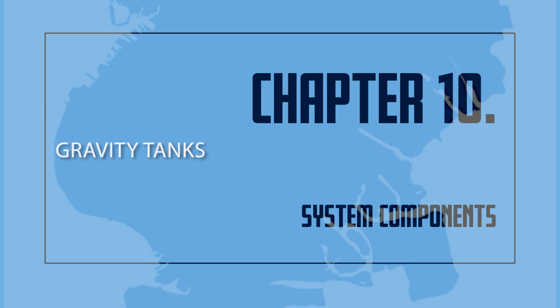All gravity tanks have an overflow pipe that drains off excess water in the tank. This happens if the floats do not turn off the fill pump. A fill pump is not necessary if the water pressure in the city water main is able to keep the tank filled with the correct amount of water. Gravity tanks are exposed to very low temperatures. All parts of the gravity tank must be insulated or heated to keep the water from freezing. Several methods are used to heat the tank and the pipe that supplies the water.